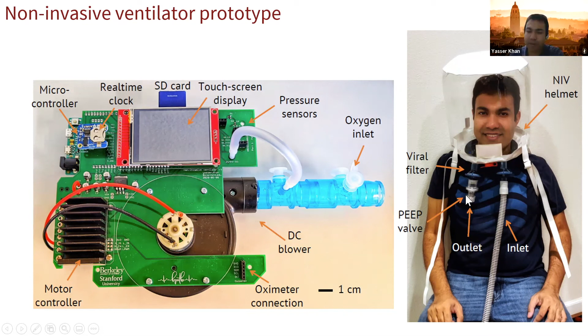And here you see on the inlet side, we have a viral filter. And also on the other side, we have a viral filter and the PEEP valve. The purpose of the viral filters is to restrict the spread of the virus. And the PEEP valve essentially contains the pressure. So you can change the pressure from the ventilator and also from the PEEP valve. And we wanted to make the UI really easy to use. Basically, you change the setting here and press start, as simple as that.